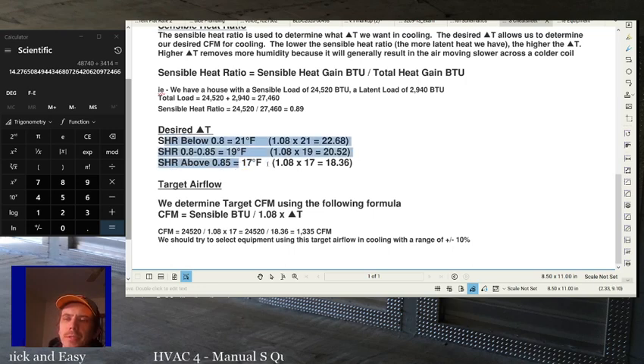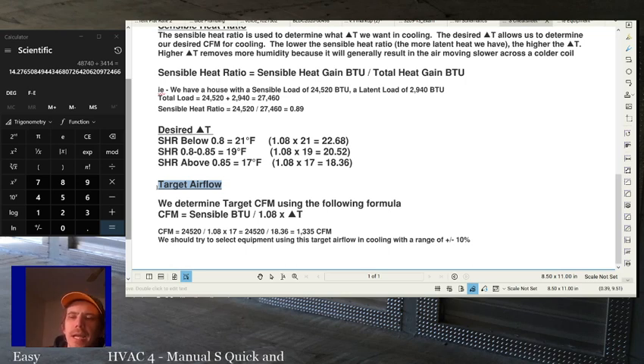So now that we know this, if we know our sensible heat ratio and we know our desired delta T based on that sensible heat ratio, now we can determine how much air we want through the equipment in cooling. So for determining CFM in heating, it's pretty simple. You go by the manufacturer's recommendations on the furnace or whatever, right? Or if you're using a boiler, obviously you're not even dealing with CFM. But when it comes to a gas furnace, you want to kind of pick a CFM that's a nice happy medium that keeps you in the heat rise that's required for the furnace. So if you want to know target CFM for heating, basically pick a number based on the furnace you pick, usually somewhere around 40 to 50 degree delta T, right?